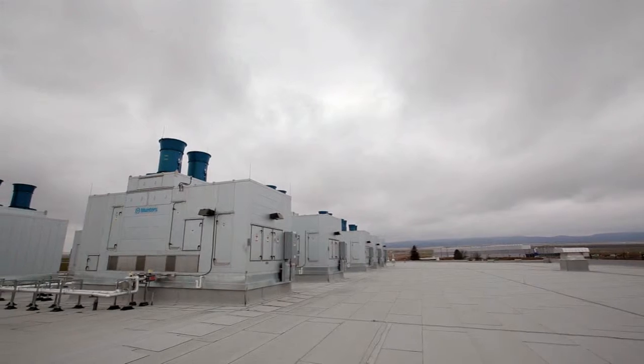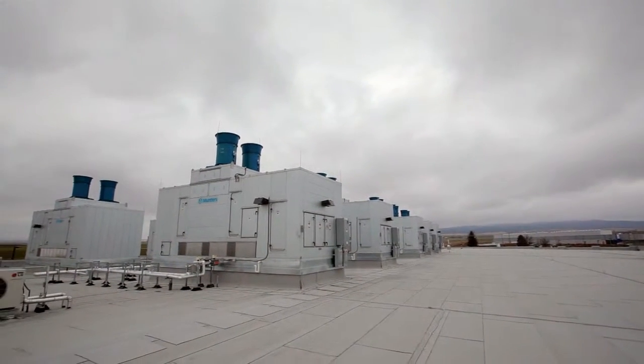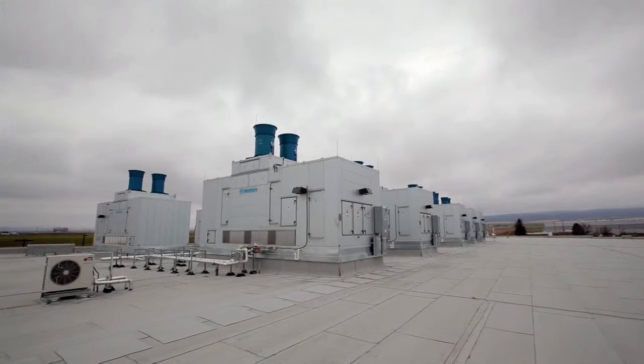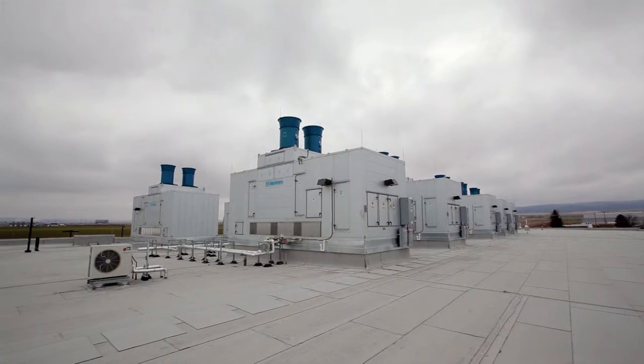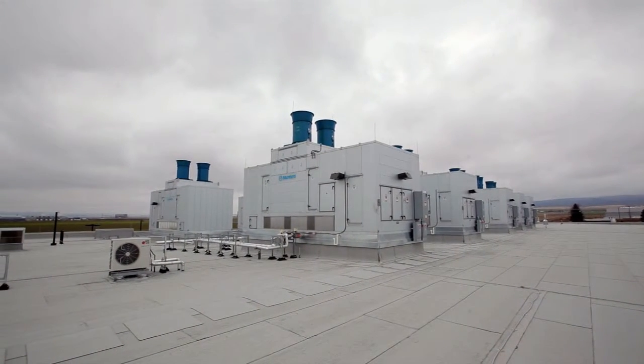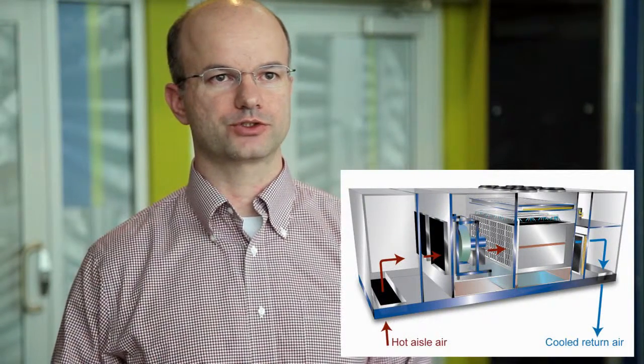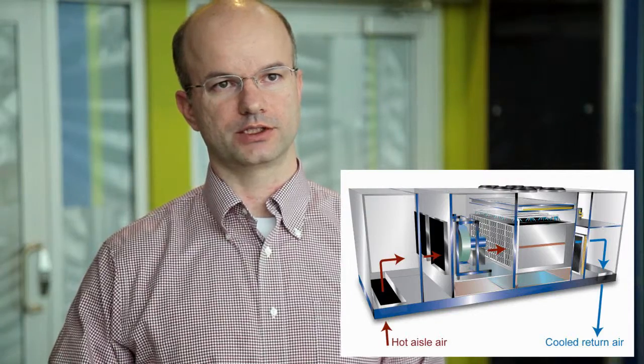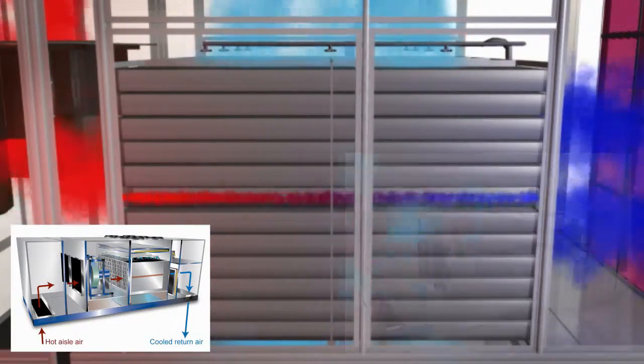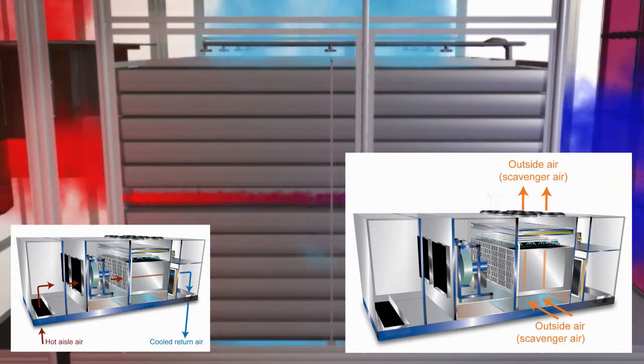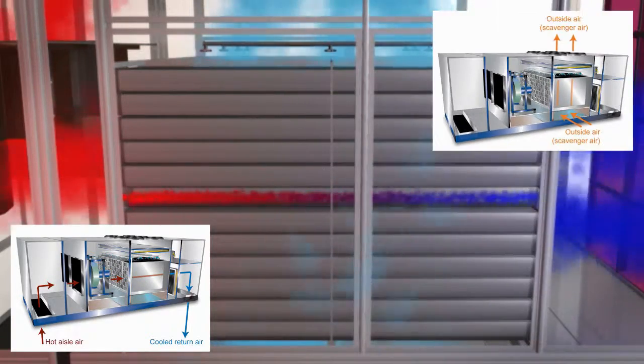So here in Quincy, Washington, we have a very good climate. It's very mild. But we have more outside air concerns than what we have in Seattle because we're in a rural area. There's a lot of agriculture around here. Some of the farmers burn their fields, they plow their fields, you get dust, that sort of thing in the air. And with indirect evaporative cooling, essentially you have two different airstreams. You have an airstream inside the data center that gets pulled through one side of a heat exchanger, and you have a separate airstream outside the data center that never enters the data centers.